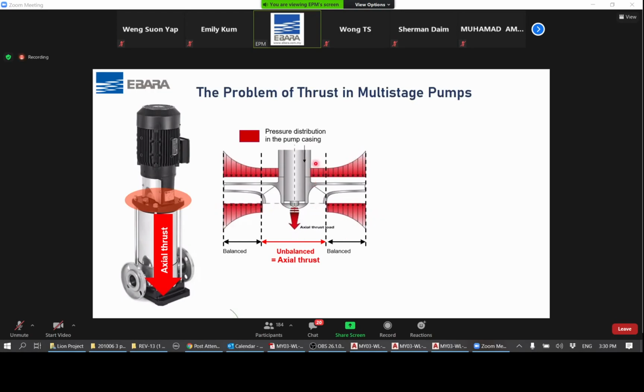So you can see the area of the zone. There's more pressure on top than the bottom. So the imbalance of pressure is causing a downward thrust because the pressure here is higher than the pressure at the bottom. Now, when you multiply this imbalance by maybe 5 or 6 or 8 stages, what you get is a very unbalanced thrust acting downwards on the pump.